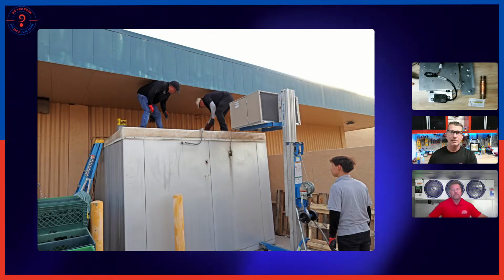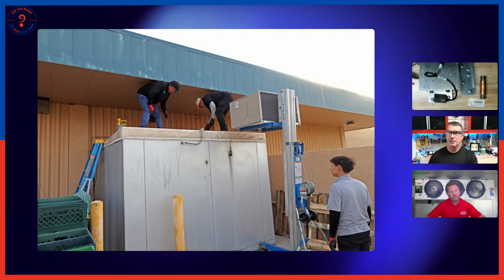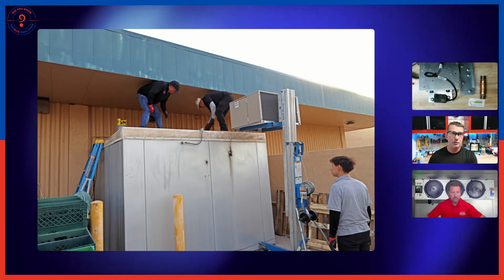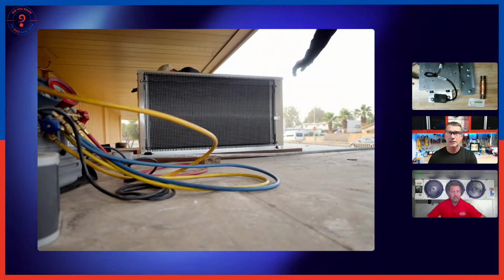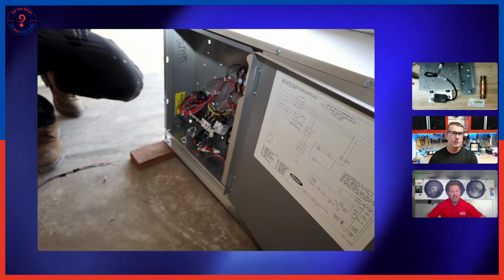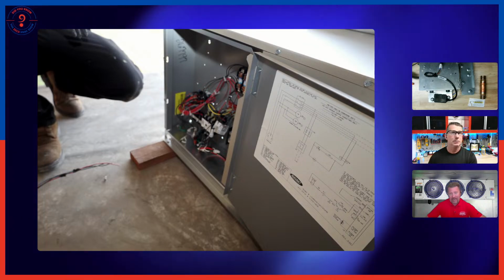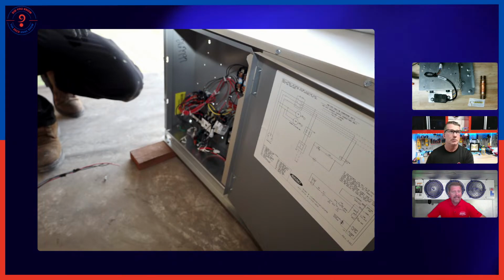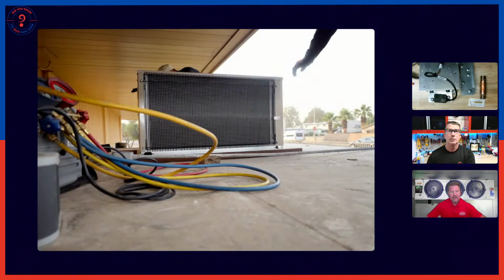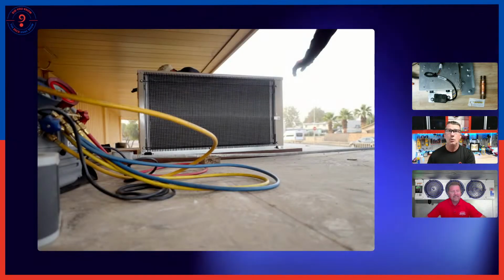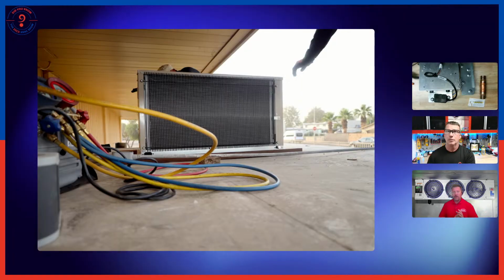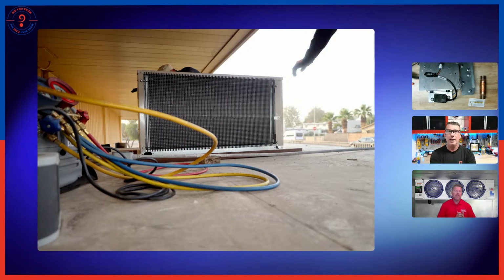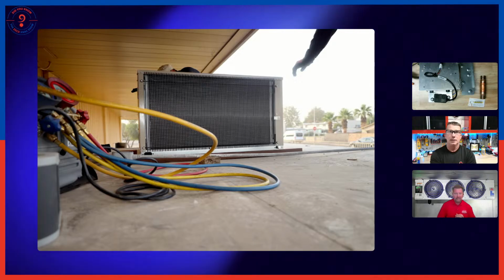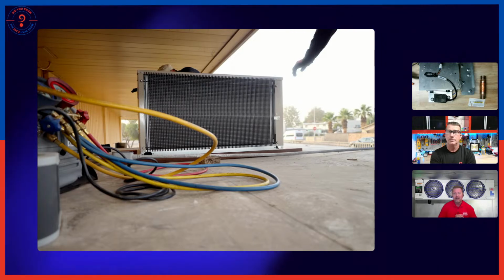Excellent. So when we look at the outdoor unit, we're really looking at just a traditional looking outdoor unit. We don't have additional refrigerant detection sensors. We don't have additional controls added to it. The main thing that was different there, if you go back to the last picture, see the grate in front? Oh, sure. That would not be on your traditional A1 condensing unit. Okay.